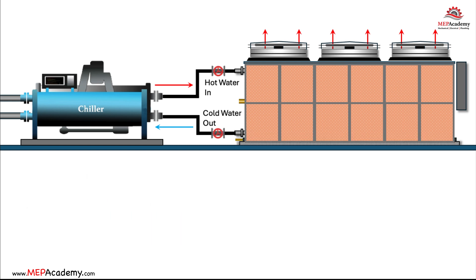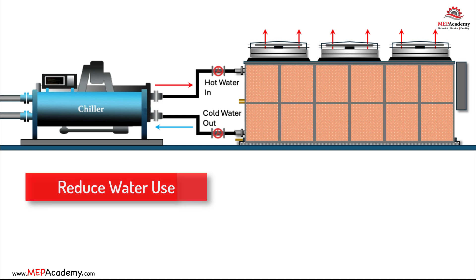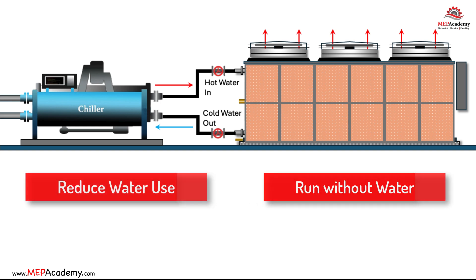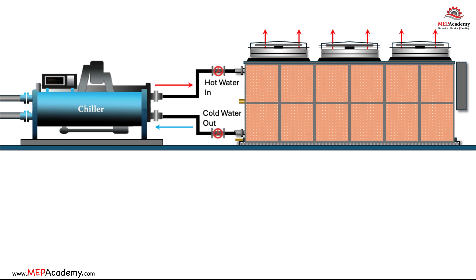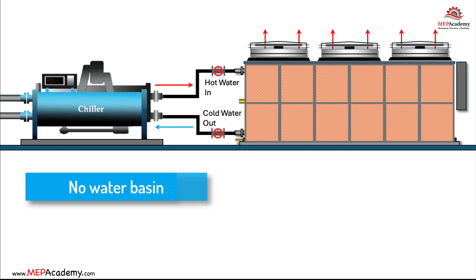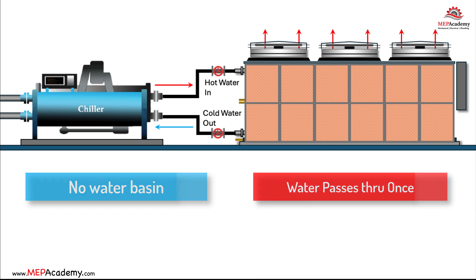The adiabatic fluid cooler can eliminate or significantly reduce water consumption compared to traditional evaporative systems. They can be operated without water until ambient conditions require additional capacity to meet demand, reducing water consumption and the cost to treat and dispose of water. There is no water basin to hold water or gather dirt and debris, as the water passes through only once and is not recirculated, so there is no need for a recirculation pump.